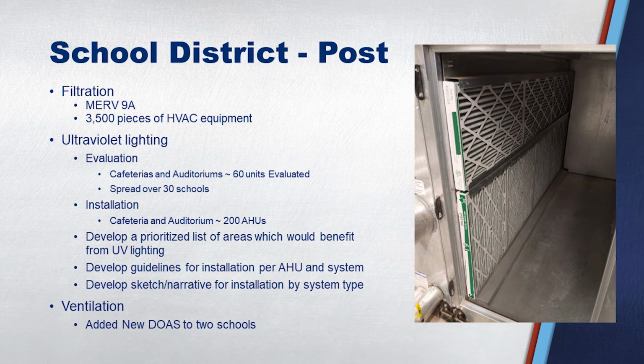So the funding they went after was for UV as well as filters. And so we did some evaluations. We also looked at ventilation. So what they ended up with is, because, like I said, we had a good knowledge on their systems and it was a lot of deferred maintenance, we said, use a MERV 9A filter because all of your equipment will be able to run on that.